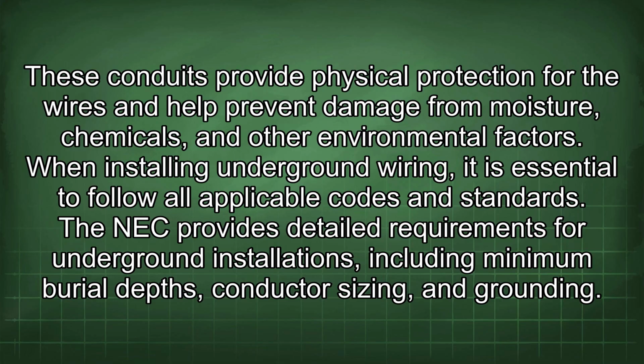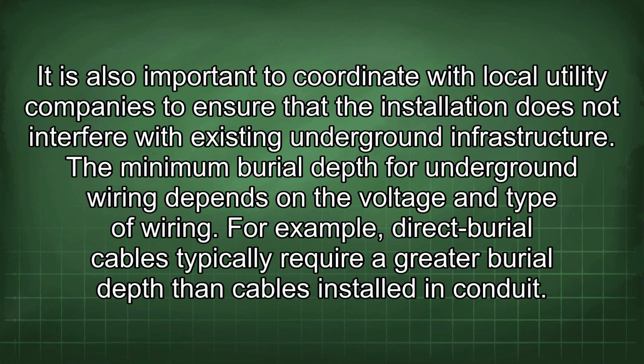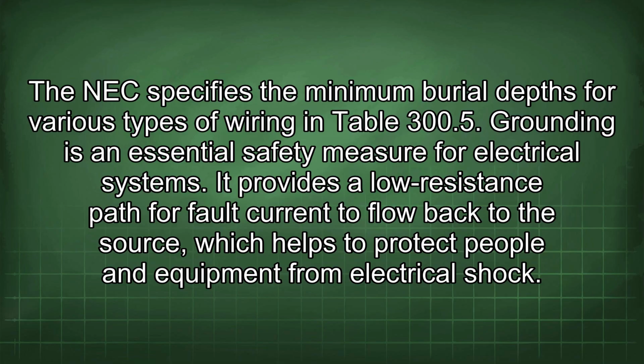When installing underground wiring, it is essential to follow all applicable codes and standards. The NEC provides detailed requirements for underground installations, including minimum burial depths, conductor sizing, and grounding. It is also important to coordinate with local utility companies to ensure that the installation does not interfere with existing underground infrastructure. The minimum burial depth for underground wiring depends on the voltage and type of wiring. For example, direct burial cables typically require a greater burial depth than cables installed in conduit. The NEC specifies the minimum burial depth for various types of wiring in Table 300.5.